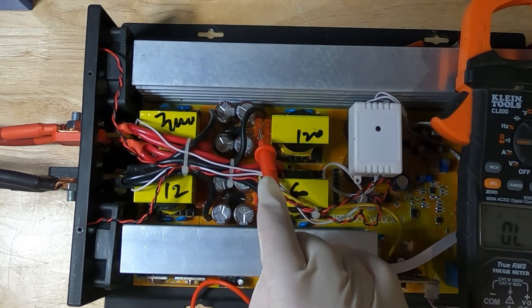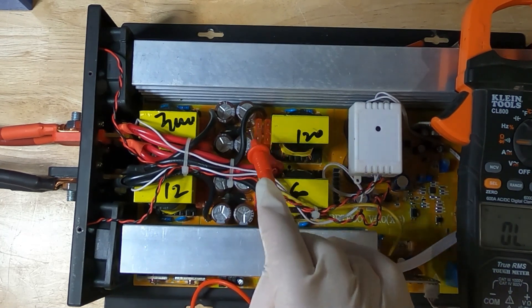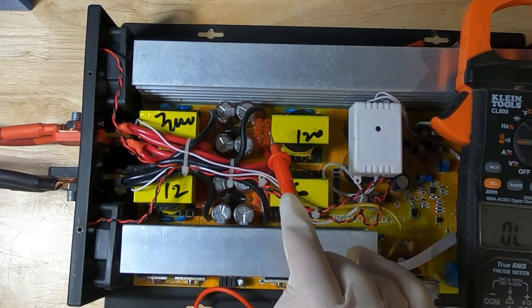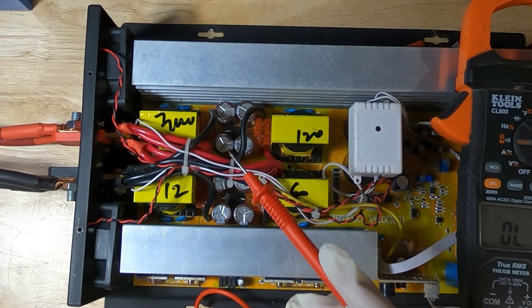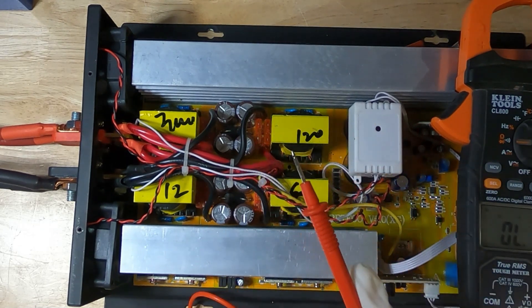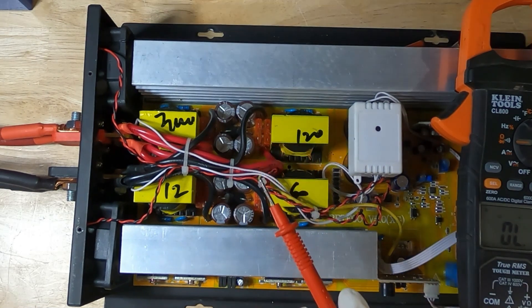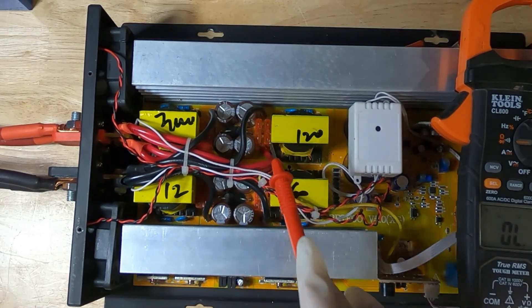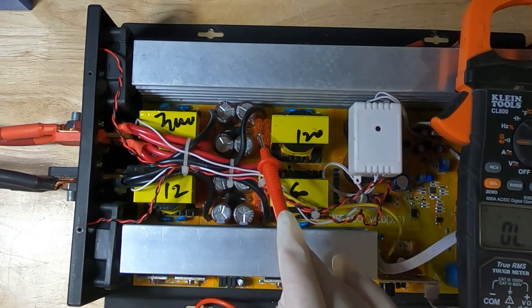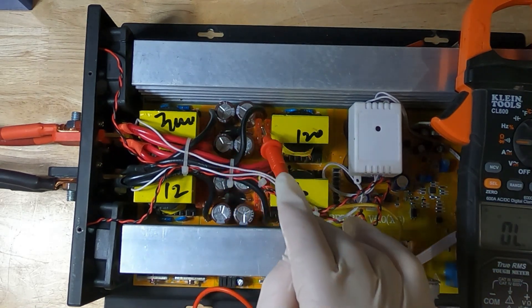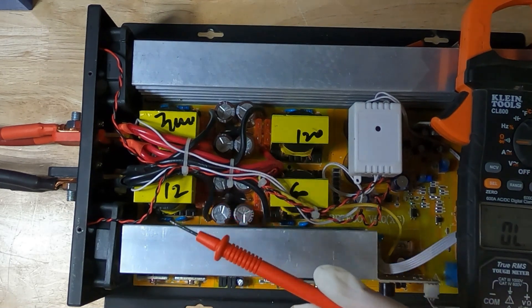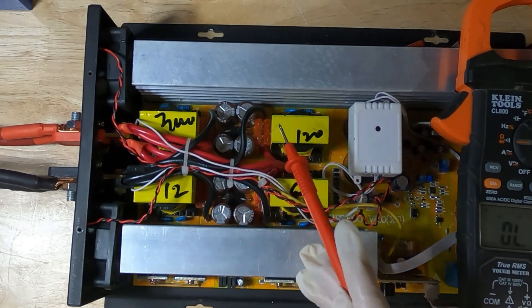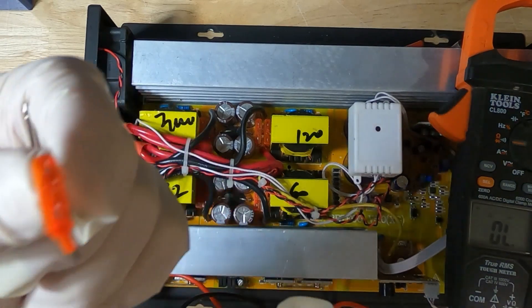If only one fuse is blown and you go to do your test, you may not know that the other fuse is blown because the inverter can actually operate as I was saying before. But there was no AC output, so we're looking for two of these to be blown. You may have to test individually all of them—actually pull them out of their sockets and test them—because of the way these are connected in parallel.